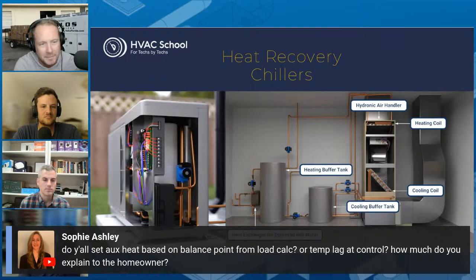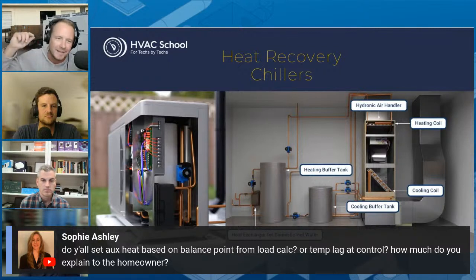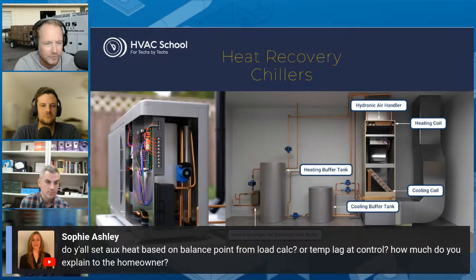If they would just leave it be, then the thermostat lag would really dictate when your heat strips need to come on. When it starts to slip by 2 or 3 degrees, the client's not going to be happy unless they start to get a little additional heat in there, which is why, and this is your traditional heat pump setup where you have auxiliary heat in place. But what you're really trying to prevent is if that client comes in and they let it get real cold in the house and then they smash it up, you don't want the heat strips to come on in those sort of situations. Anybody else have any other thoughts there?